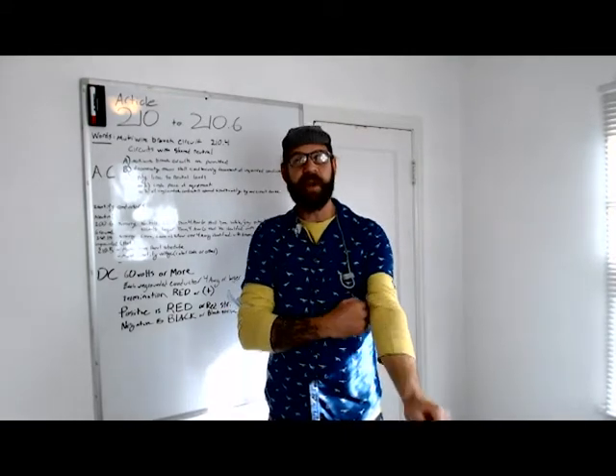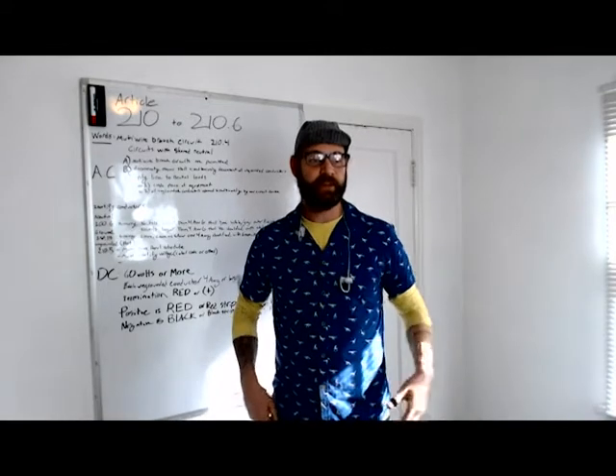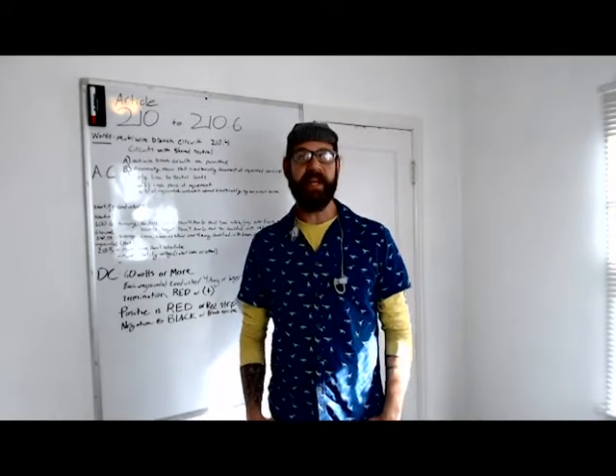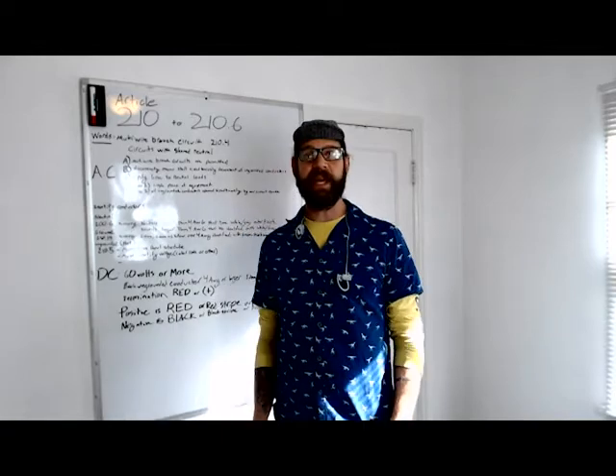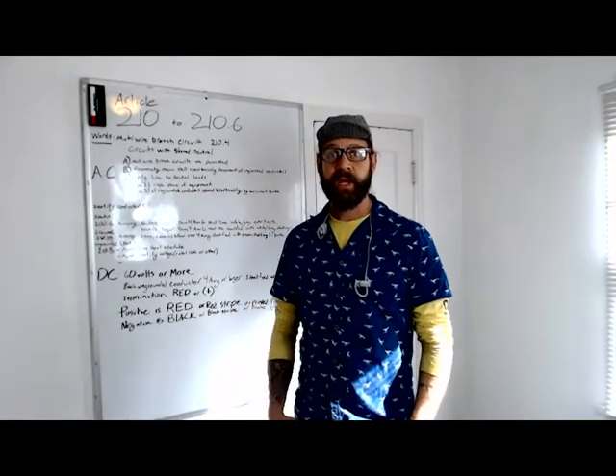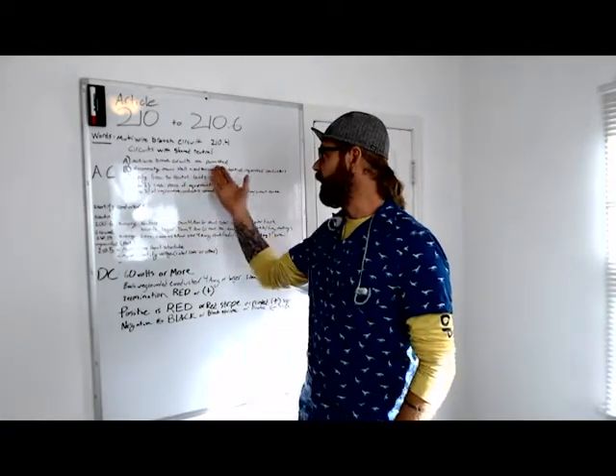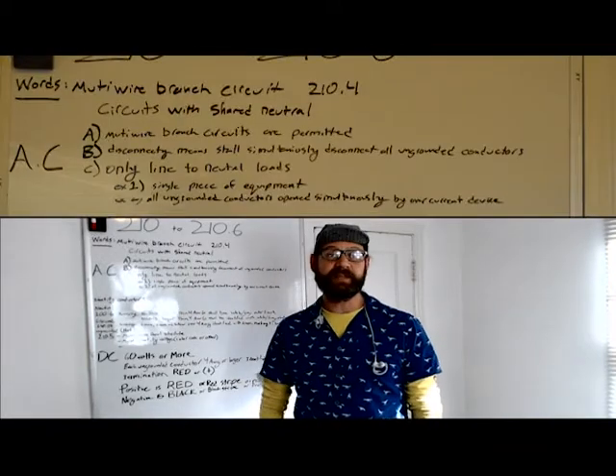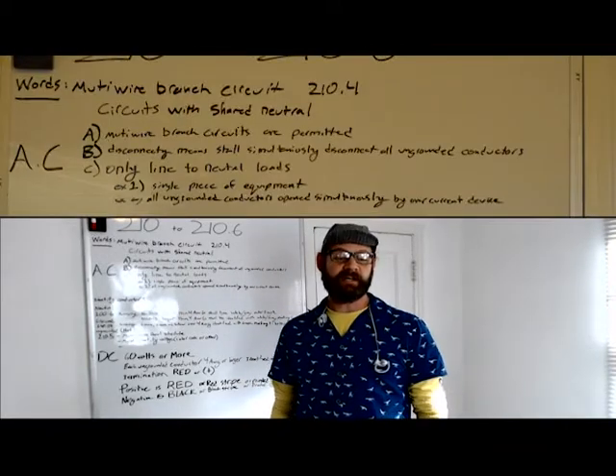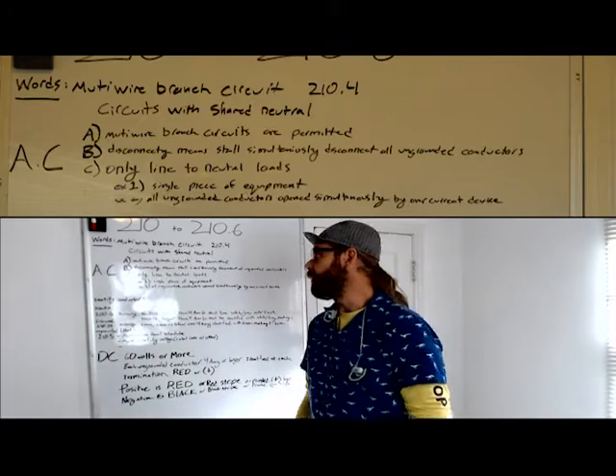This used to be real common. They used to run 3 hot wires per neutral, and that's just the way they did it. And although we don't do it that much anymore, according to the code, it shall be permitted. It is a permissible way to install electrical wire.